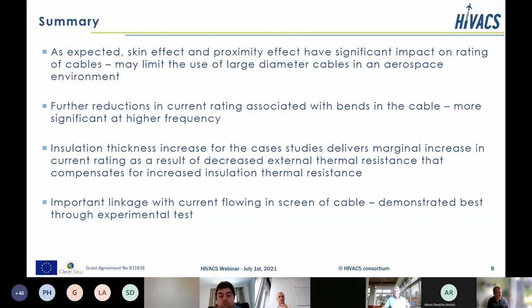And as I've just said, the insulation thickness increase actually delivers a marginal increase in the current rating and not a decrease. There is, though, this big important linkage, as has already been picked up in some of the questions, about the current flowing in the screen of the cable with what that means in temperature rise. And some of that is best demonstrated through experimental test.